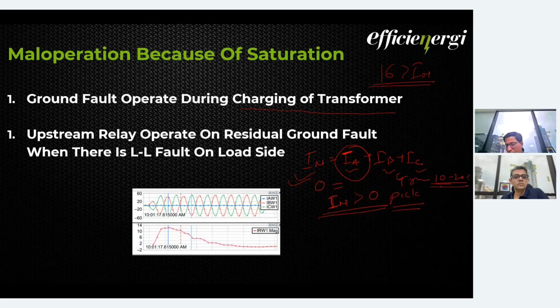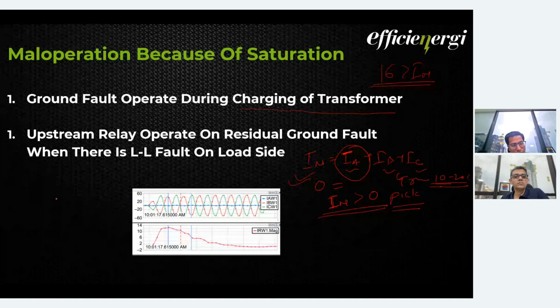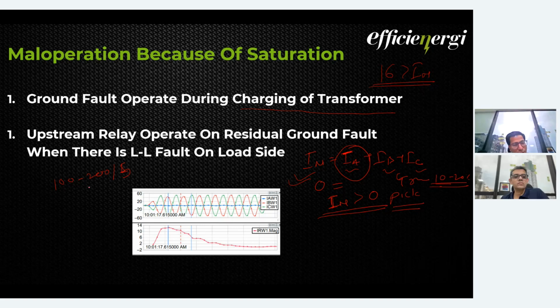So in some of the projects, and we now see this in many projects, the transformers are, let's say, of 2000 kVA or 2500 kVA. The CTs at the primary are normally in the range of 100 ampere to 200 ampere by 1 or by 5. Okay. So because now the network is getting bigger, at the 11 kV side or at the 33 kV side, the fault is maybe in the range of 20 to 30 kilo ampere sometimes.